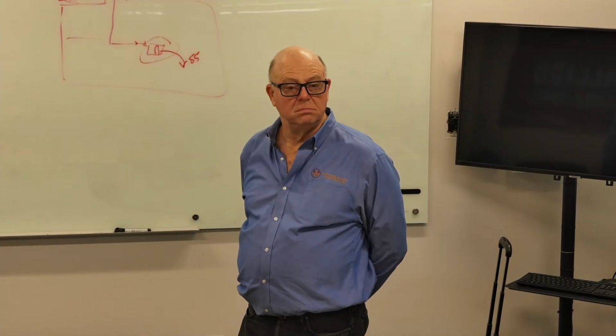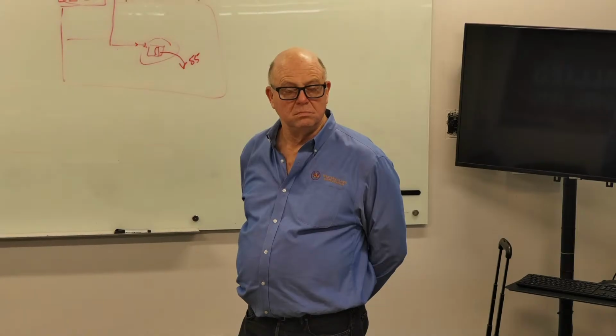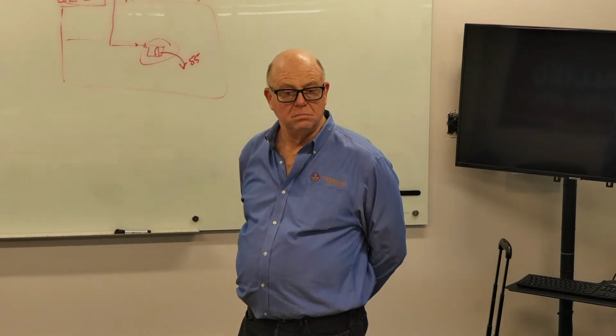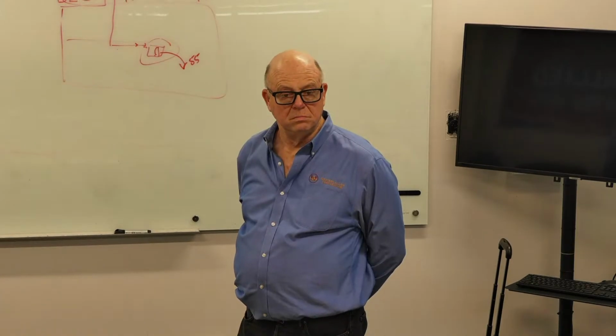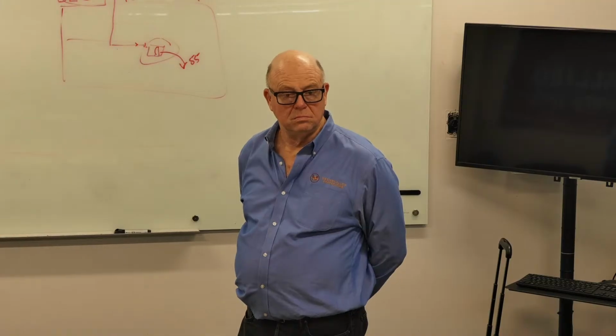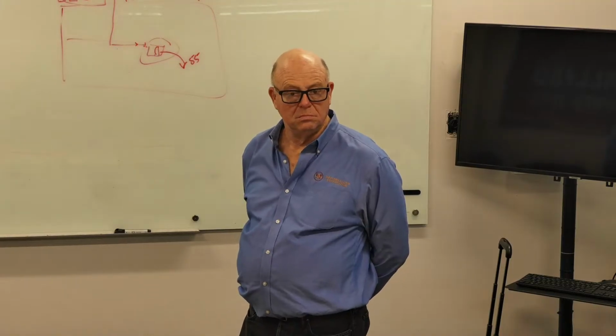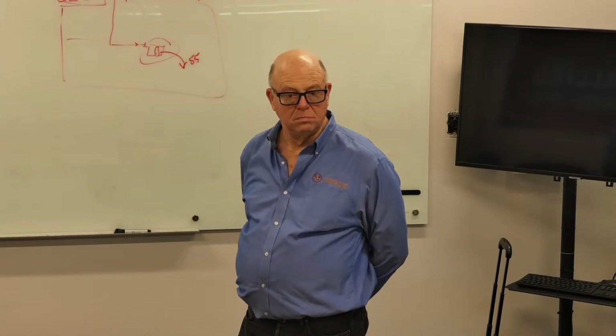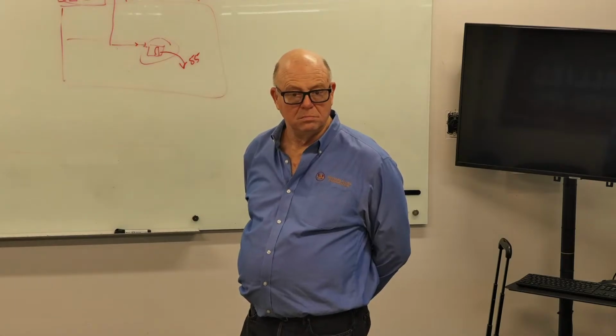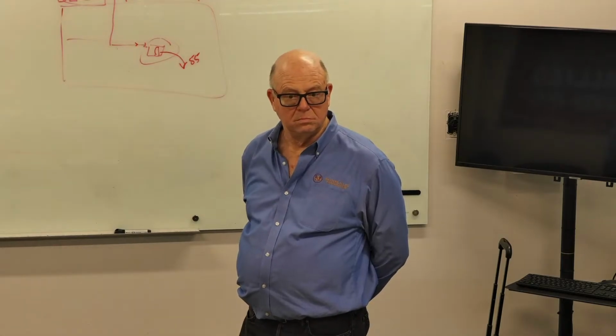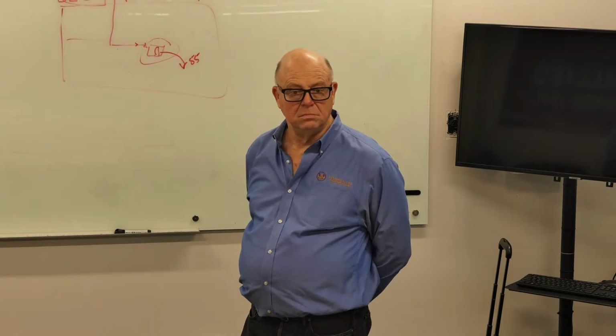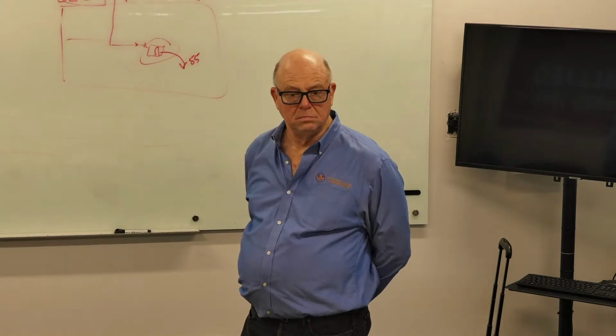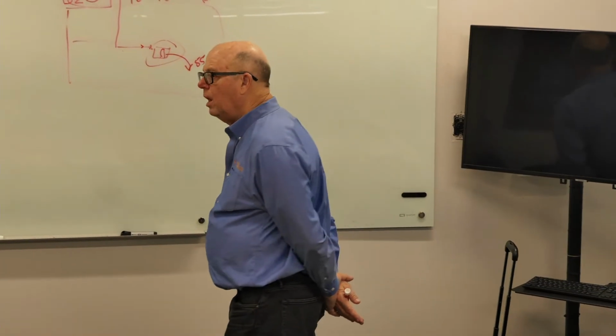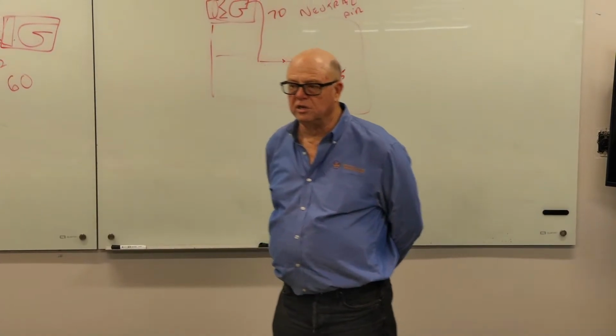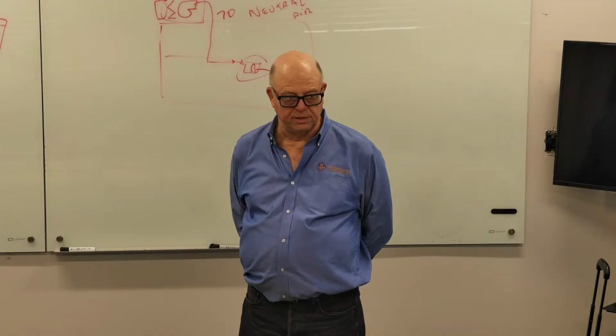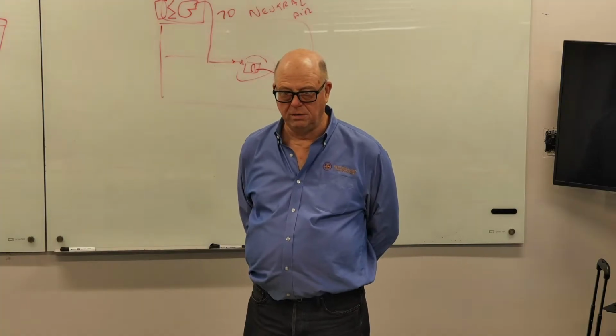I don't know if it's a question, but we had a problem once where the server room, I think they didn't duct it correctly because they had 2 units in the server room, and it was more like half the room was done by this one and the other half by that one, rather than intertwining the supplies. So if I use the expression hot aisle, cold aisle, does everybody know what I'm talking about?